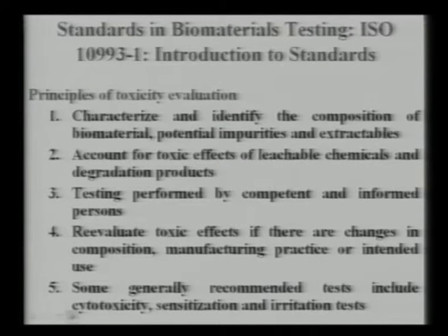Okay, we'll start with that 10993-1, the set of guidelines which will tell you what tests you need to carry out for a specific application. Now the principles of the toxicity evaluation essentially characterize and identify the composition of the biomaterial and the potential impurities and extractables.